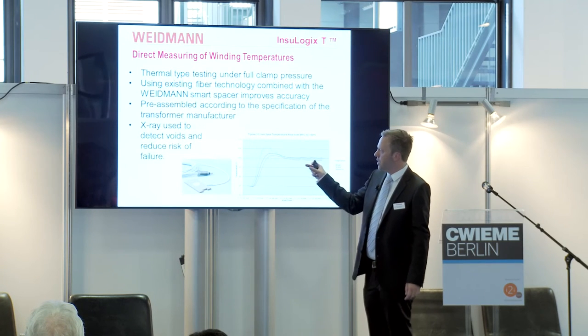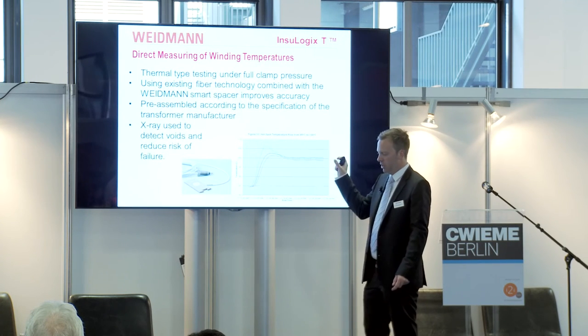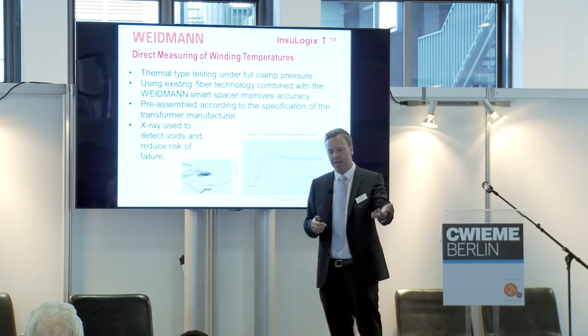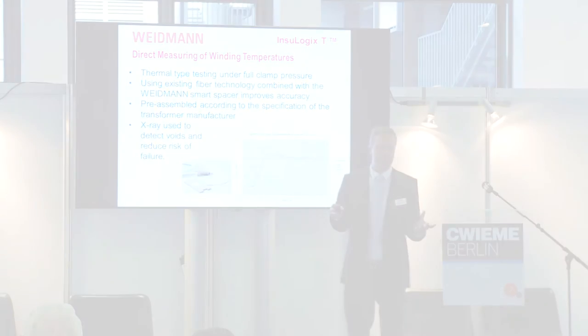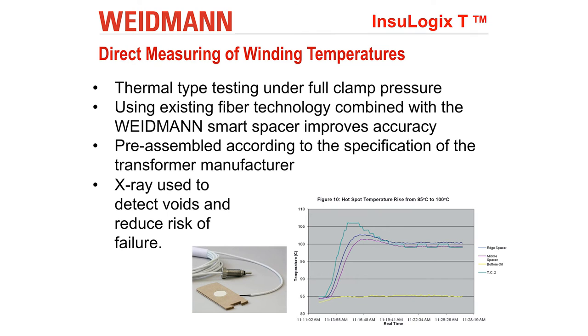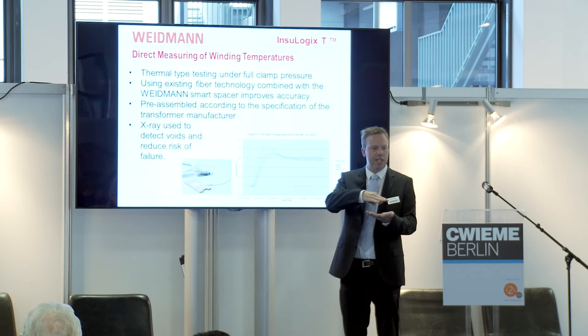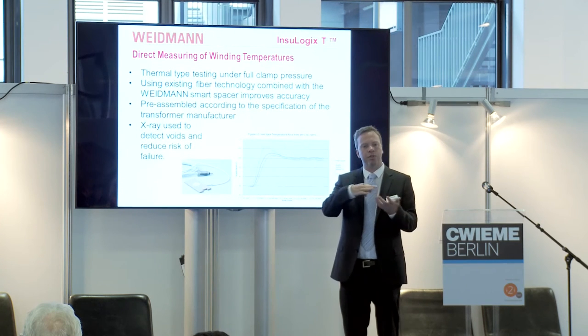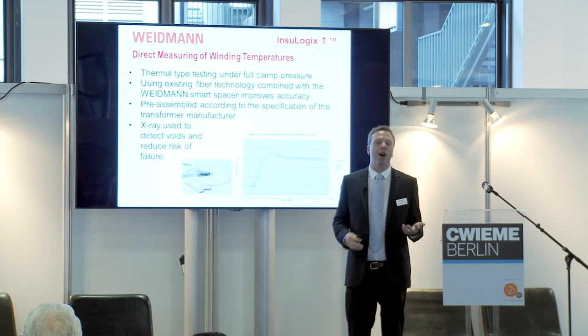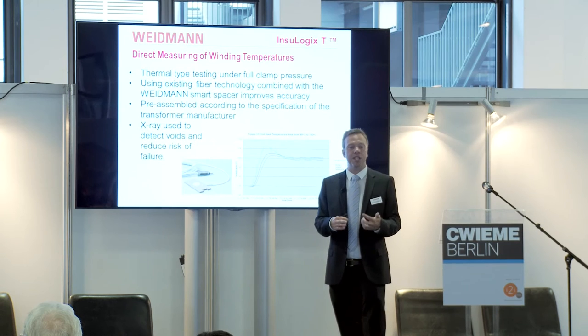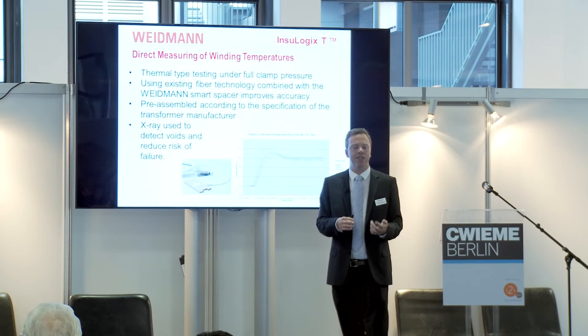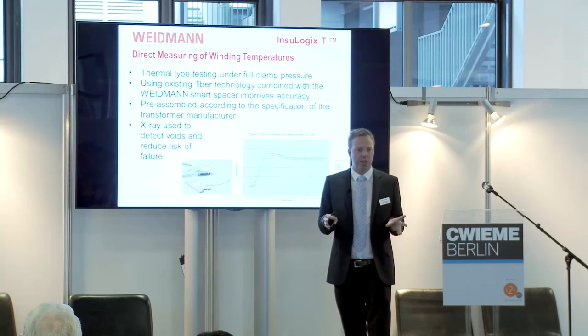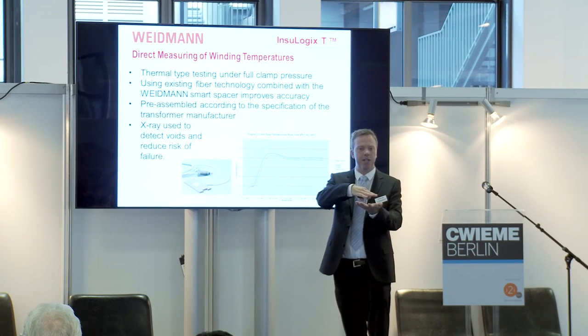And the spacer itself is pre-assembled by Weidmann, who manufacture hundreds of thousands of spacers per year. But what we do is we actually use our existing technology. So we use compression testing on this. We X-ray it, we look for voids in it and so on, to try and ensure that once it's installed in the transformer, it has a limited failure rate. So we don't want fiber breaking, or the spacer failing once it's put under pressure.